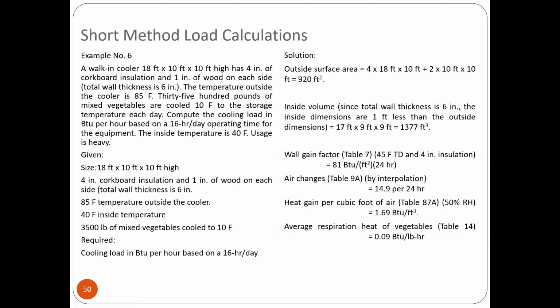A walk-in cooler, 18 feet by 10 feet by 10 feet high, has 4 inches of corkboard insulation and 1 inch of wood on its side, total thickness 6 inches. The temperature outside the cooler is 85 Fahrenheit. 3,500 pounds of mixed vegetables are cooled 10 degrees Fahrenheit to the storage temperature each day. Compute the cooling load in BTU per hour based on 16-hour per day operating time for the equipment. The inside temperature is 40 Fahrenheit.